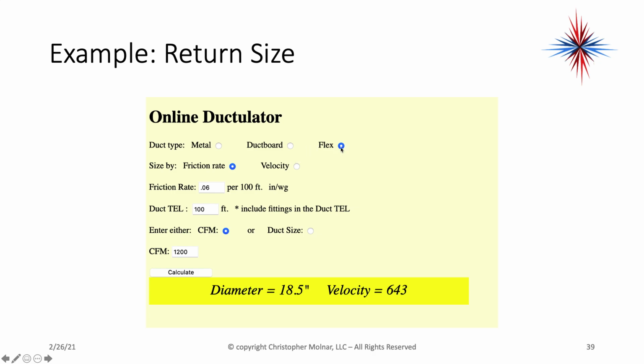We have flex duct. Make sure you choose the correct type of duct. I want a friction rate of 0.06 per 100 feet. I'm going to use CFM, and I want 1200 CFM. You click the calculate button. I need a diameter of 18.5 inches, and my velocity is going to be 643, which, believe it or not, is a little bit high for a return filter. If you look at the specs of the filter, the velocity is probably closer to looking for a 300. So right there, I do have a problem.